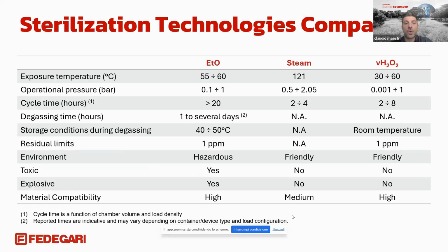Let's compare and focus on sterilization processes for heat-sensitive materials. As we can see here on the table, ETO is highly effective, but it leaves toxic residue, requires long aeration times, and faces growing regulatory restrictions. H2O2, on the other hand, decomposes into just water vapor and oxygen, leaving no harmful by-products. It's faster, cleaner, and more sustainable. The trade-off is that H2O2 penetration can be more challenging in complex geometries. But, as we will see on the next slides, with deep vacuum technology, we have been able to overcome those limitations.